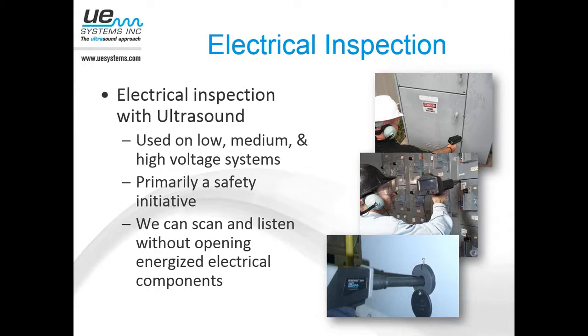So one of the things that a lot of service providers and individual plants and companies globally have started to implement is scanning enclosed switchgear with ultrasound, listening for any type of problem. Typically on enclosed gear, what you end up hearing is tracking problems. And if that's heard, you don't want to open the cabinet to do the infrared inspection.